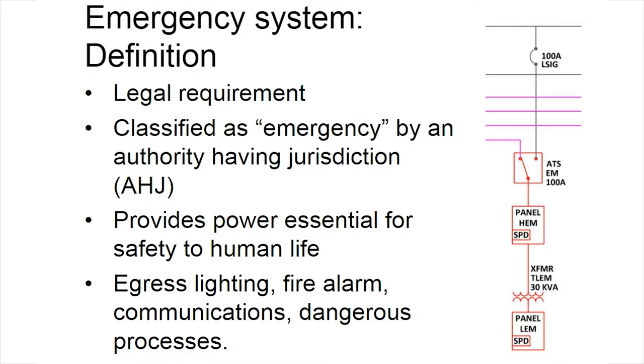The classic example of emergency load is egress lighting, and that's lighting, say, to illuminate a path to the outside of a building when the normal source of power is not available. Other emergency loads are things like fire alarm, communication systems that you might use to contact emergency services like the fire department, or that provide emergency instructions to the occupants. Industrial processes that can't be shut down unexpectedly without some serious danger to people are also considered emergency loads.